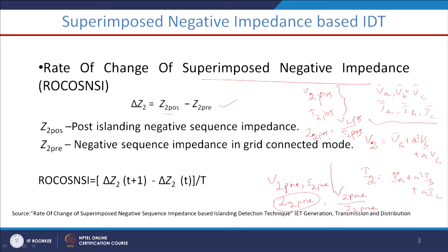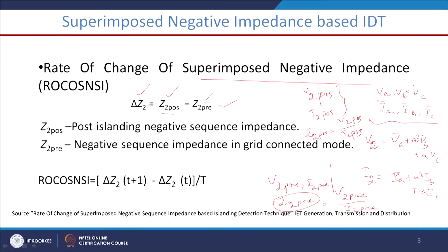After getting Z2_post (after the disturbance) and Z2_pre (before the disturbance), the difference between these two impedances is known as the superimposed negative sequence impedance. The superimposed term means the difference between the post quantity and the pre quantity — that is, superimposed parameter = post parameter minus pre parameter.